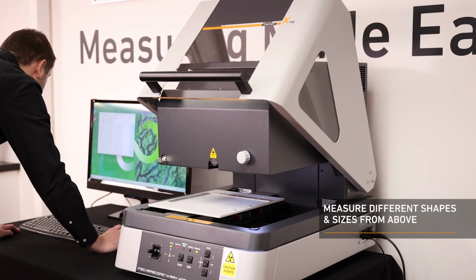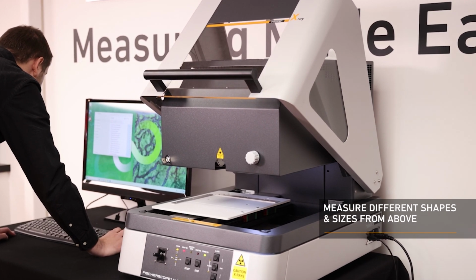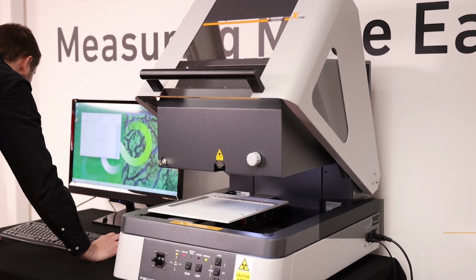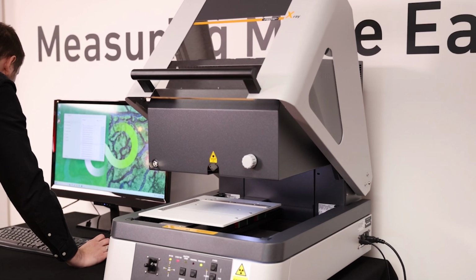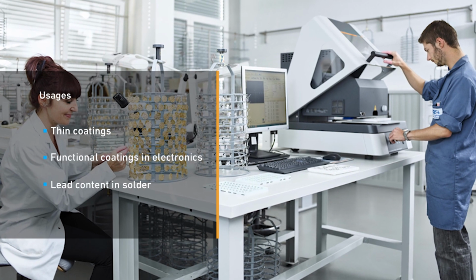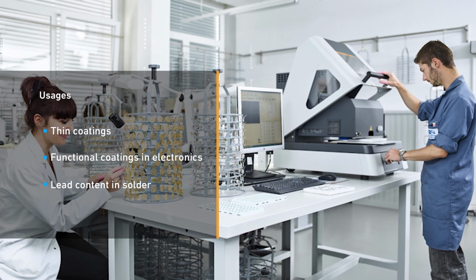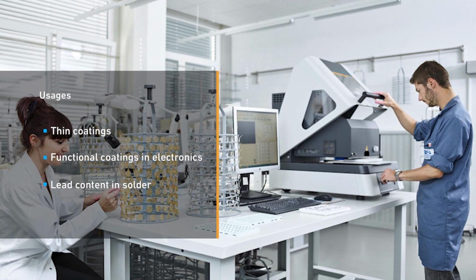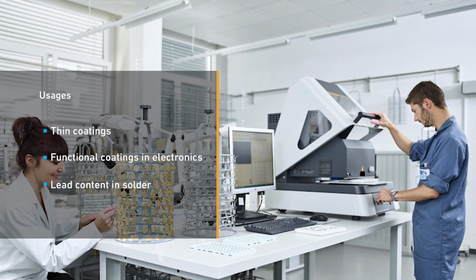The instrument has an X-ray beam in a top-down measuring direction, so samples are measured from above. Typical fields of application include the analysis of very thin coatings, functional coatings in electronics, complex multi-coating systems, and determination of hazardous materials in RoHS screening.